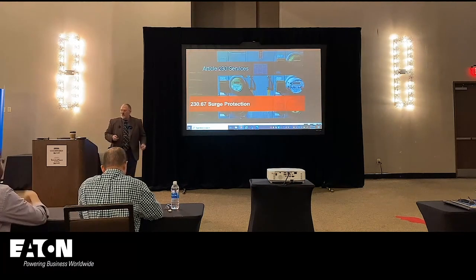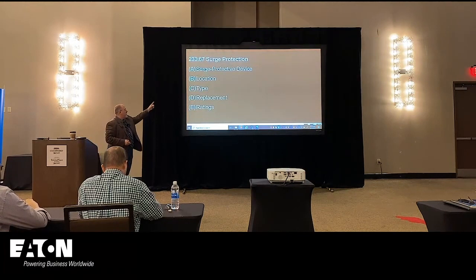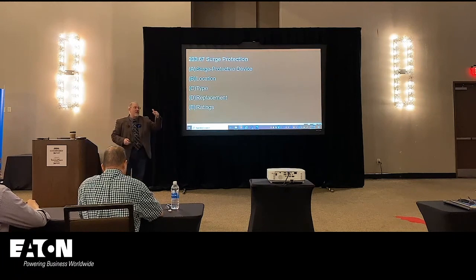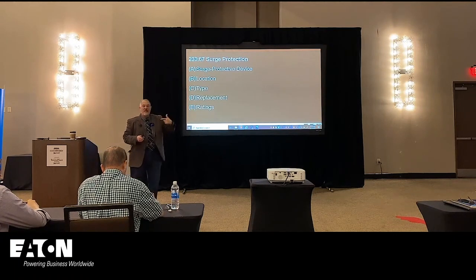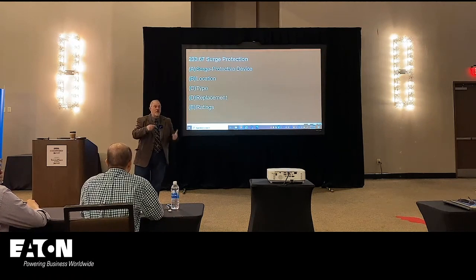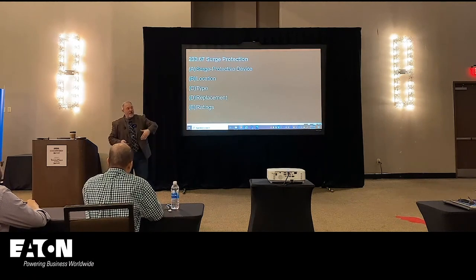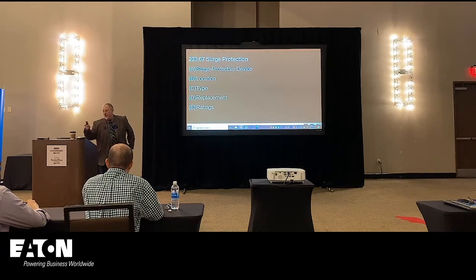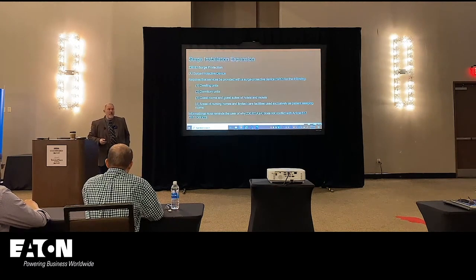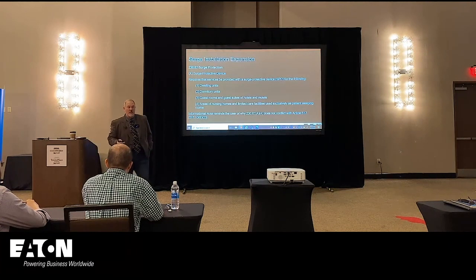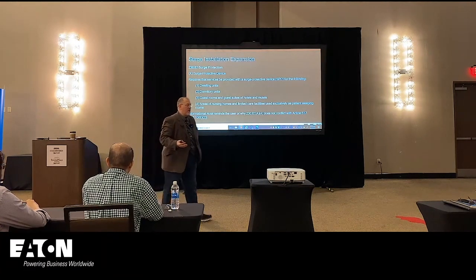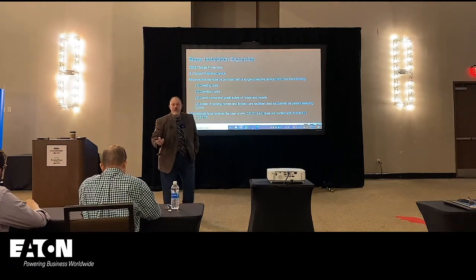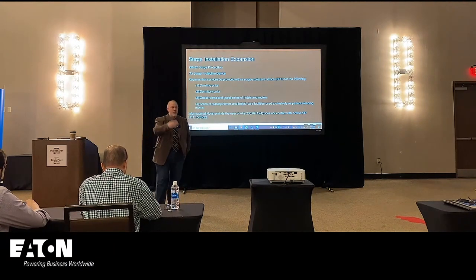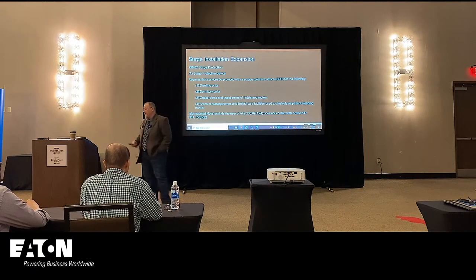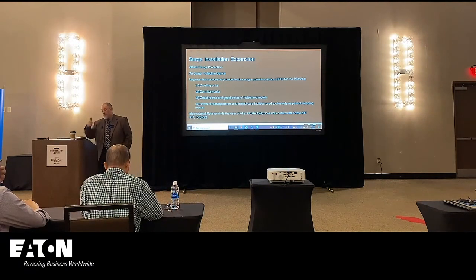So here's how we did it. 230.67: you have surge protective device requirements, you have the location, you have the type, the replacement. So we addressed that if you update a service, and say it was from the 50s, we want you to put surge in for the new service. Also the feeders, etc., and the type, replacement, and the ratings. One of the big complaints that we got was that you put surge requirements in, but you didn't tell me what the rating needs to be, right? Because you can buy a surge device and it may not do what you think it's going to do, just because of how it's constructed and what some of the parameters are.